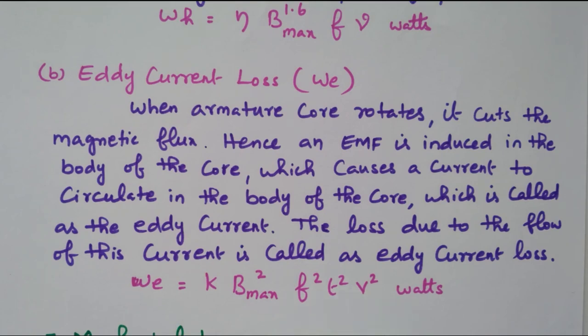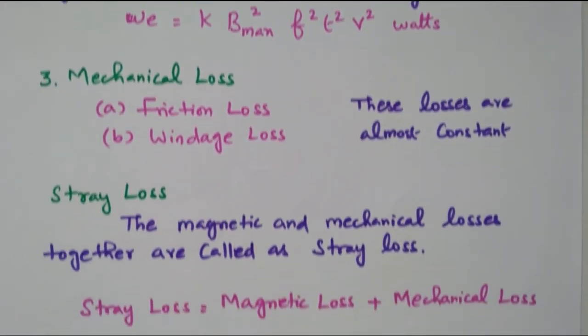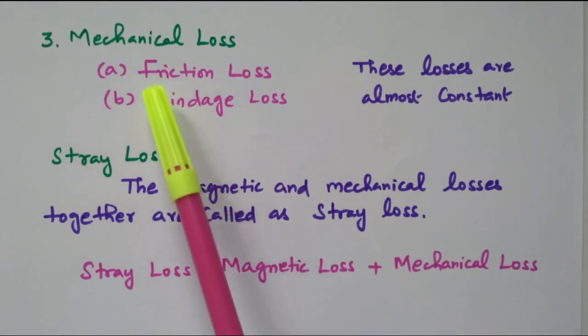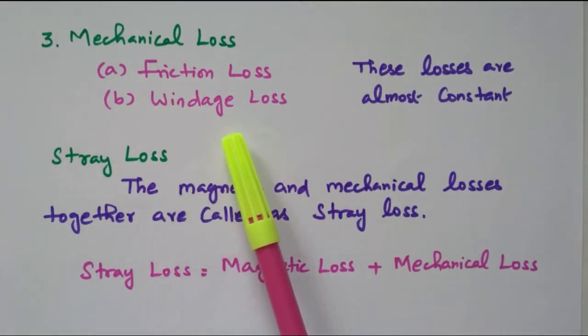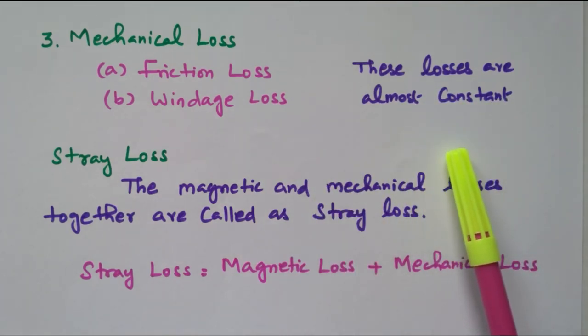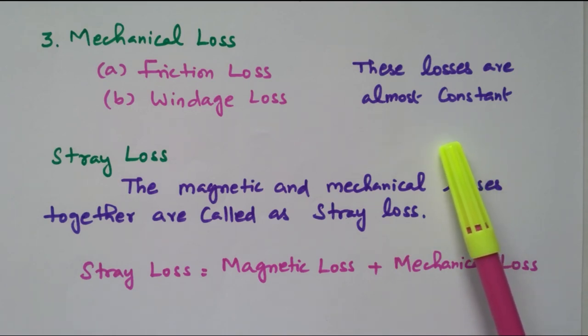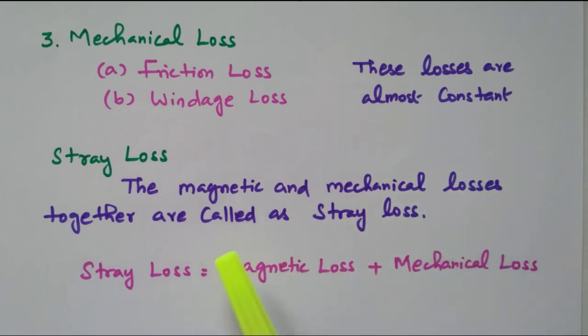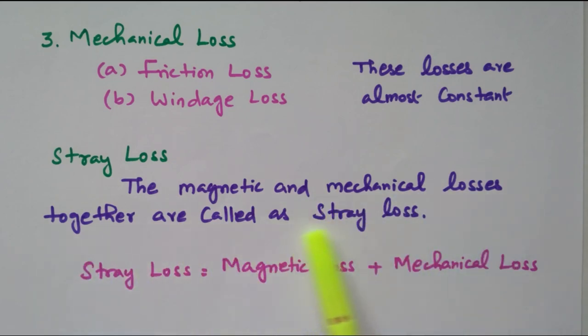The third loss is the mechanical loss — friction loss or windage loss. These losses are almost constant. So: first, copper loss; second, iron loss; third, mechanical loss. The second and third are almost constant. Iron loss and mechanical loss are constant. One more classification is available: stray loss. The magnetic and mechanical losses together are called stray loss.